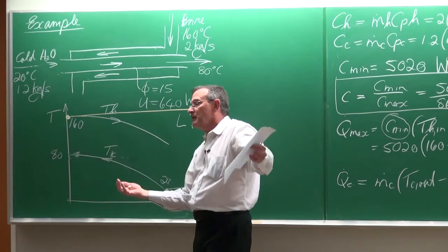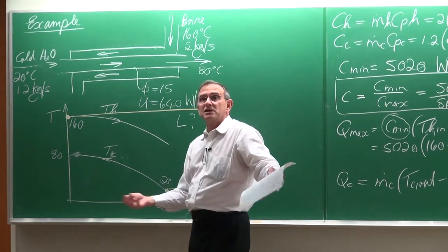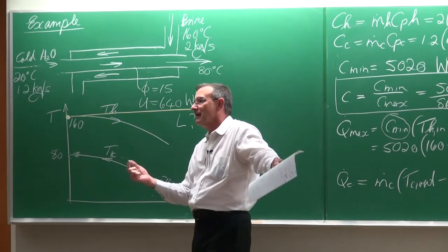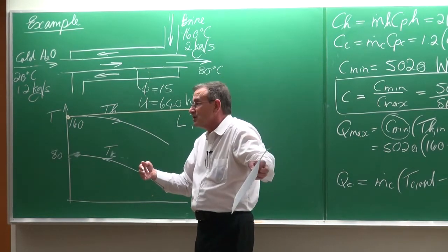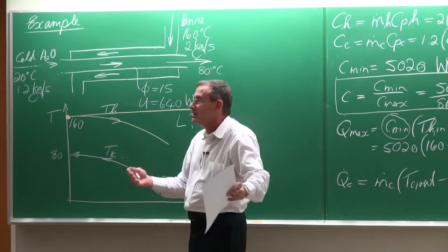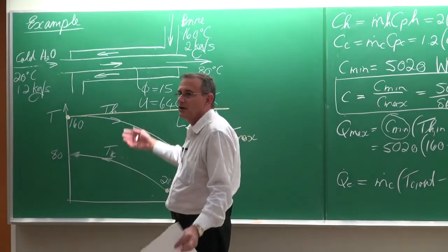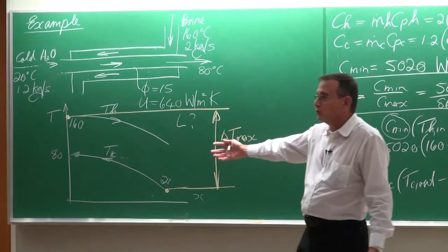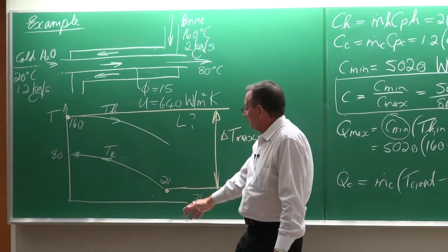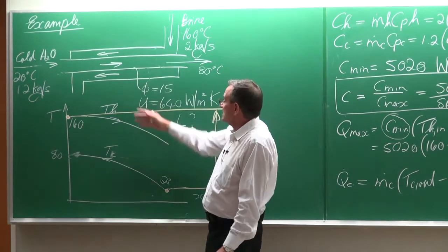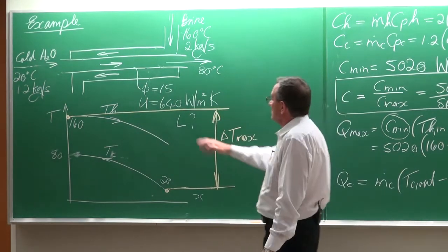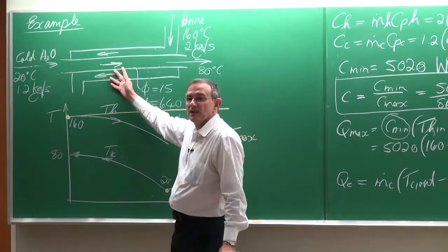It is an uncomfortable thing. If you must get it into this building, 108 meters, you can't bend it. Obviously, you can get it in while you're busy with construction. You can put it in, but if you need to replace it, it's a very long thing, not something very nice to work with. So typically, these types of lengths would obviously not be practical if you want this type of heat transfer with these types of inlet temperatures and mass flow rates.